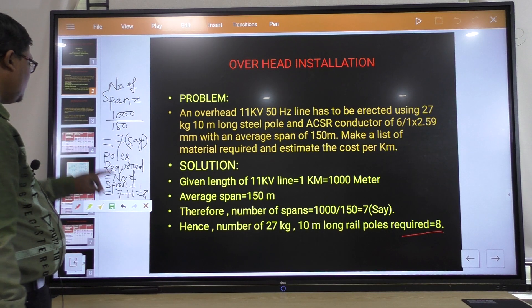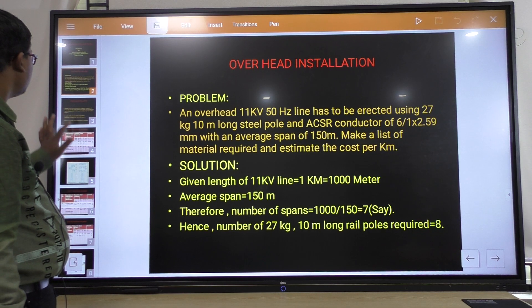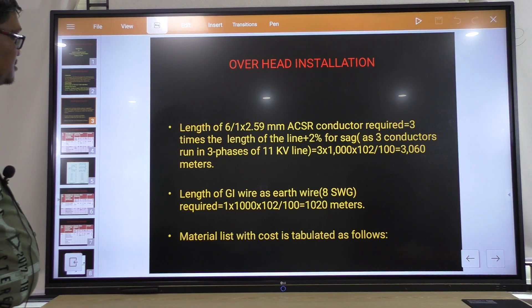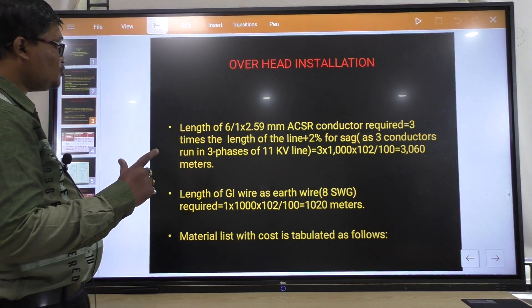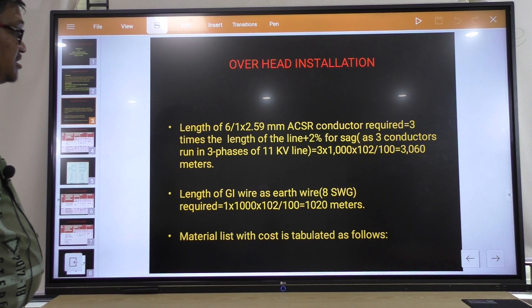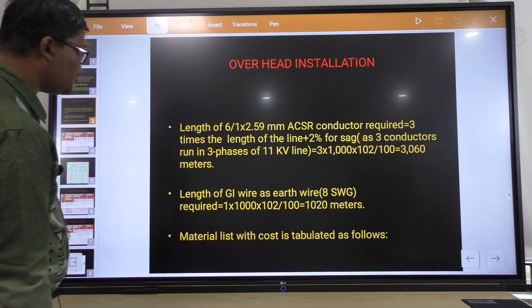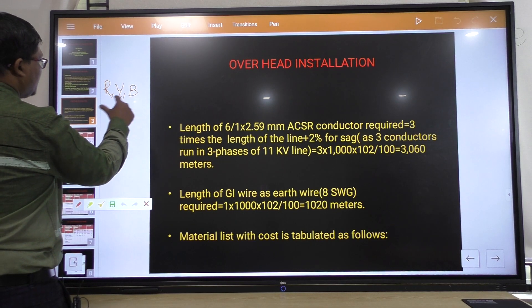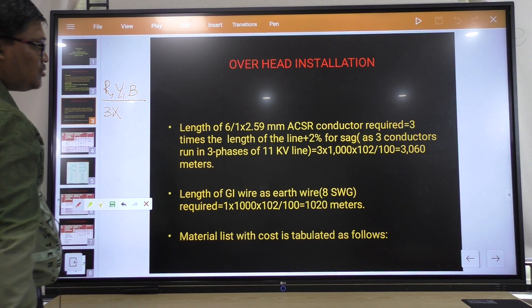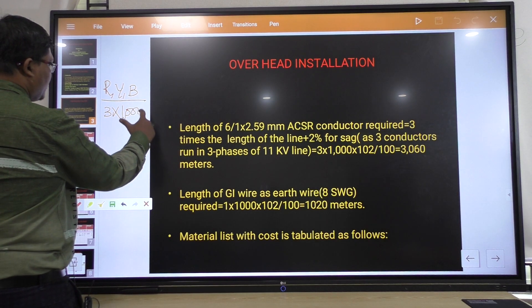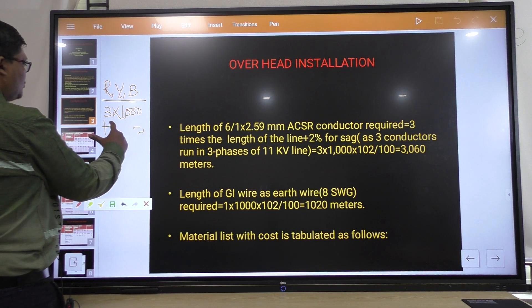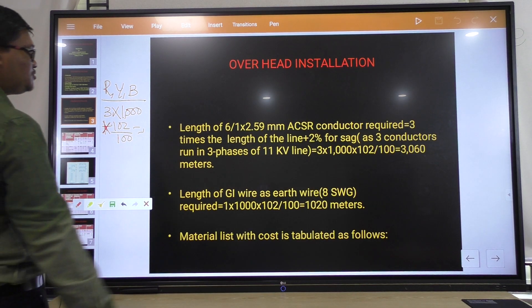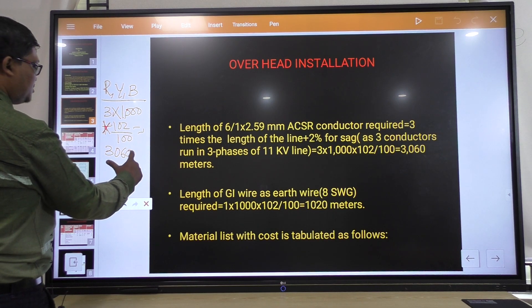Next important material: the length of 6 by 1 into 2.59 mm ACSR conductor required is 3 times the length of the line plus 2 percent sag. That is 3 into 1000 for R, Y, B — 3 phases — and plus 2 percent sag, meaning multiplied by 102 by 100. It comes to 3060 meters.